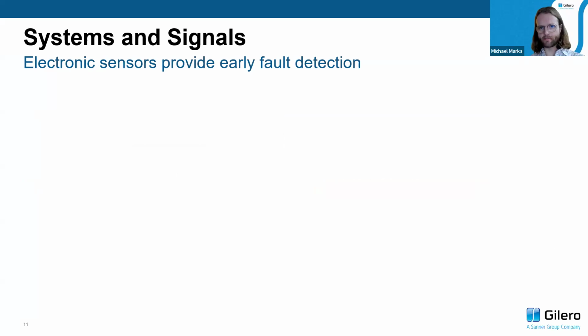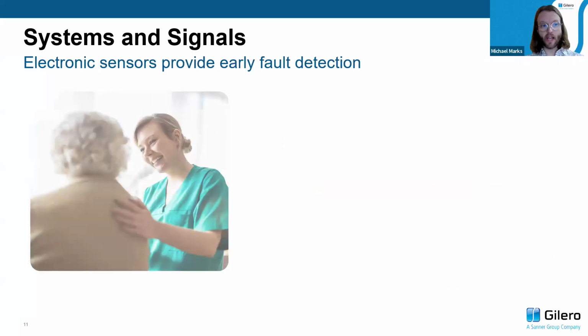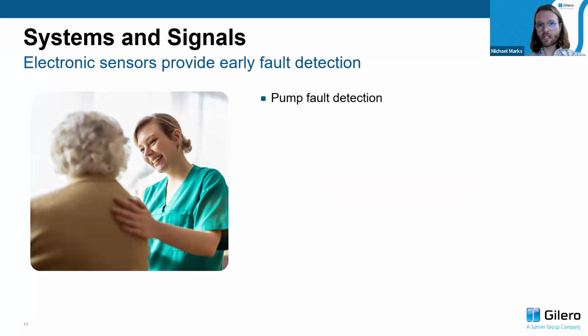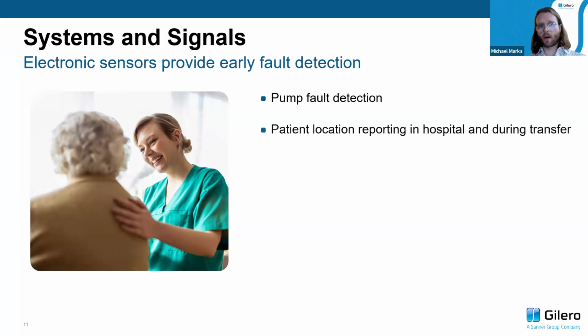So electronic sensor integration into medical devices has enabled much earlier-stage fault detection than we ever had before. You can imagine that conventional pumps and drug delivery were a kind of feed-forward control loop: you had a known pressure, and you were administering a known amount of drug. But now, with the integration of all these electronics, the miniaturization of processors, and the increasing capabilities of electronic sensors, be they optical, electronic, ultrasonic, etc., they've really enabled things like pump fault detection and patient location monitoring in a hospital much better than they ever could have been. Now we have air-in-line sensors that are ultrasonically able to detect bubbles down to the size of 0.1 milliliters in line.